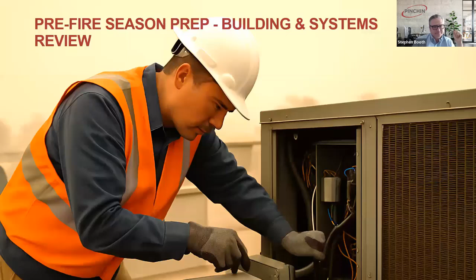It's really important to do a building envelope review. So conduct a walkthrough, identify those potential infiltration pathways that we talked about earlier. Look at the window and door seals, look at utility penetrations, roof hatches, elevators, exhaust intakes, vestibules and lobbies. All those kinds of things are those sites. So, is the weather stripping on all the doors intact? Is it intact on that roof hatch? Those kinds of things are things that potentially get missed. And then take the time to seal those before the problems become an issue during a smoke event.